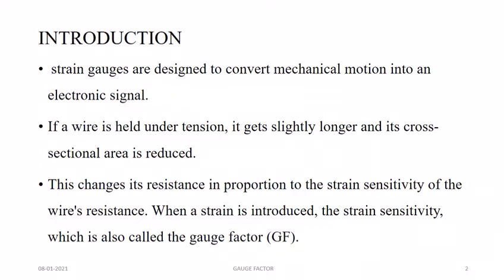If we apply a tension to the wire, it is slightly elongated — that is an increment in its length. So the length increases and the cross-sectional area will be reduced — that is a decrement in the cross-sectional area. There is a change in resistance in proportion to the strain sensitivity of the wire's resistance. This strain sensitivity is also called gauge factor, which is denoted as GF.